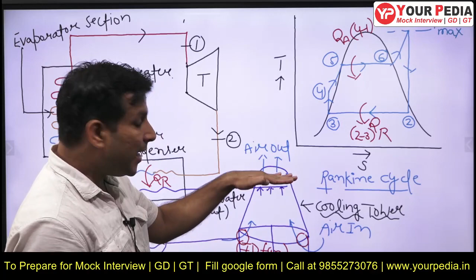But in the real case we provide induced fans here. We install ID fans here, students, ID fans. And what do these ID fans do? They force atmospheric air into the cooling tower, and when that air flows upward into the cooling tower, from the top we spray hot water, so there will be direct mixing of the air and hot water. Some amount of the water will be carried out by the air in the form of vapor only.